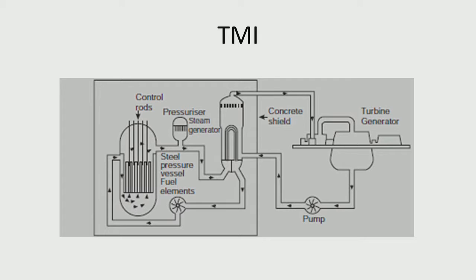Three Mile Island is a pressurized water reactor. You have the core here — it's not steam but pressurized water — it goes through, exchanges heat in a steam generator and comes back. There is a pressurizer which maintains the pressure of the system. We want higher pressure so that boiling is avoided in the reactor core. That is the uniqueness of the pressurized water reactor.